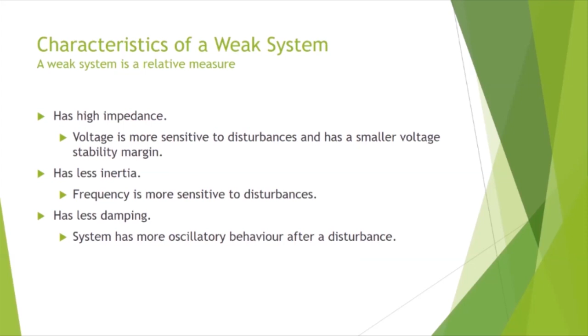Now, as I mentioned, engineers are very comfortable with synchronous generator characteristics. We understand it. So one natural tendency to control the converter is to say, okay, let's try to control the converter like a synchronous generator. That means, although there is no rotor dynamics, we can introduce rotor dynamics using equations by modeling differential equations. We can mimic the active power transfer equation and reactive power transfer equation all in software. So the converter will behave like a synchronous machine.